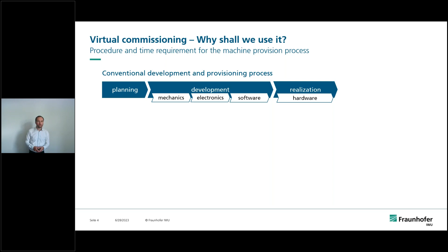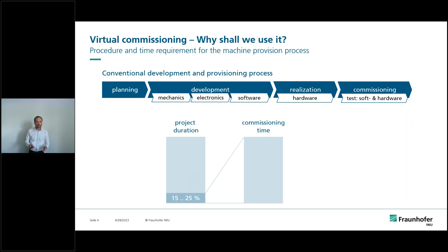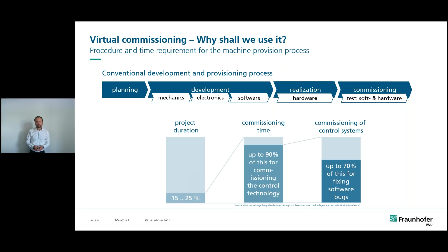If we now have a look at the project duration, we see here a bar representing it, and 15 to 25% of this time is the commissioning time of our system. 90% of this commissioning time is only for commissioning of the control technology of our machine or automation system. And 70% of this is only for fixing bugs in the controller software. So this is a big time amount where we can optimize our commissioning time if we can change our process.